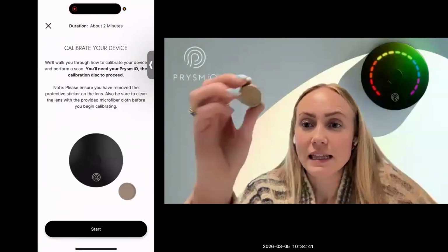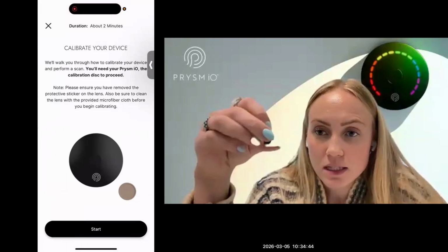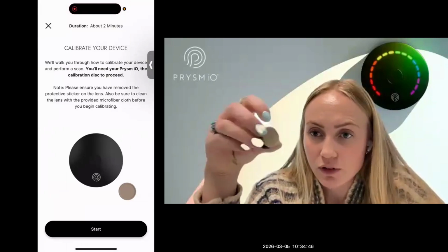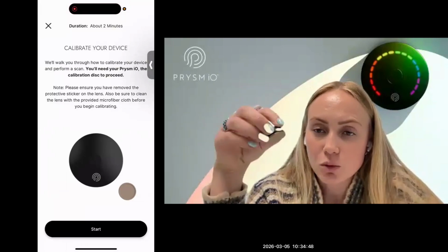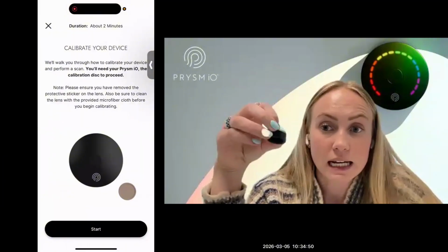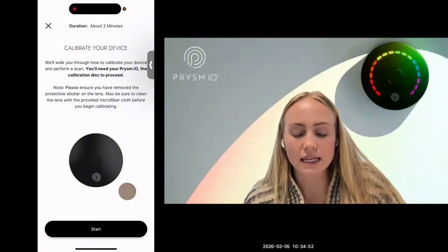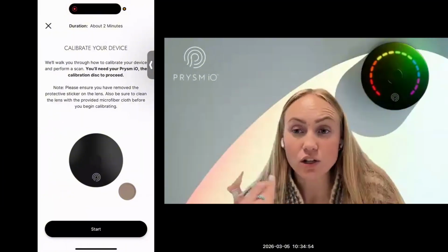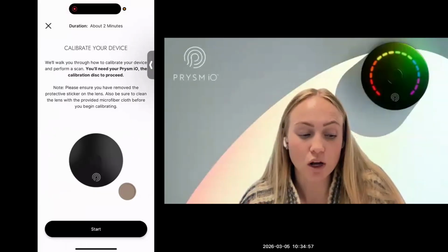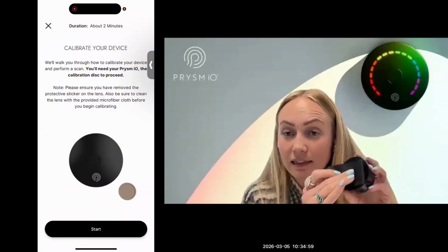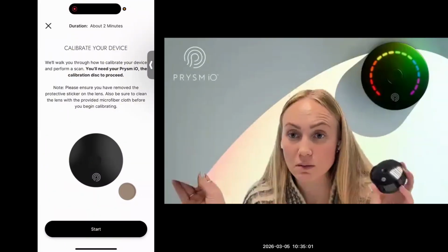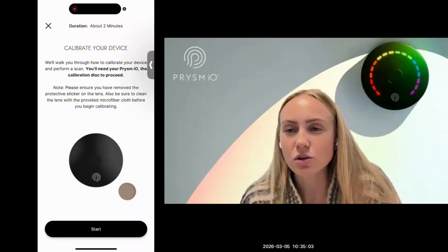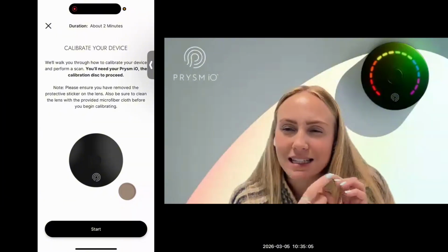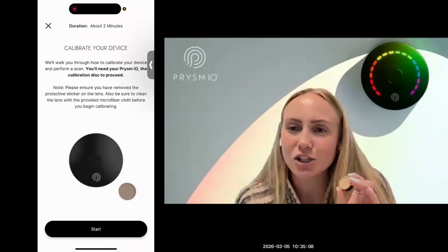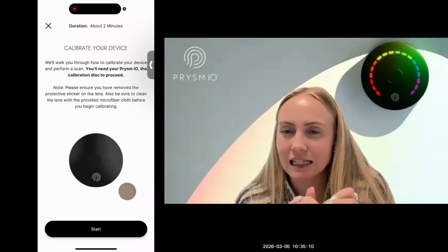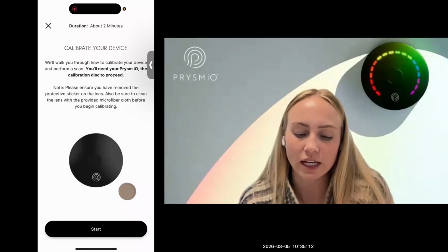You will need this calibration disc. This comes in your packaging with your device. Every device comes with one, but this is how you will calibrate it and make sure that it is scanning accurately. So what you do, as you would with normal scanning, is make sure you clean the lens with the microfiber cloth. Clean the lens before you calibrate. You also should make sure that your calibration disc doesn't have any fuzzies on it. If you keep it in your pocket, just make sure it looks clean and doesn't have lint on it.